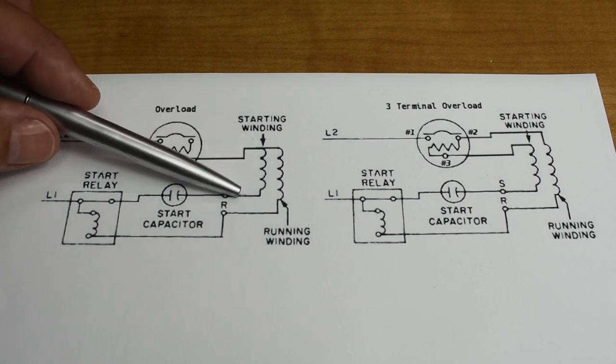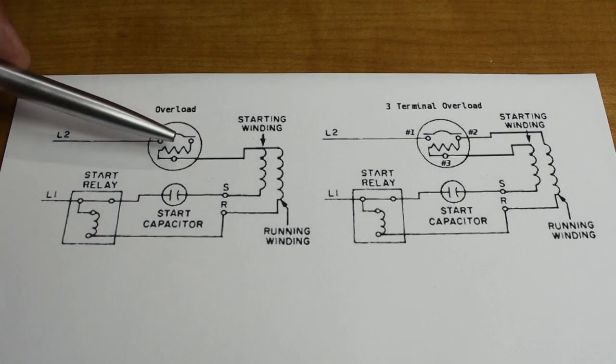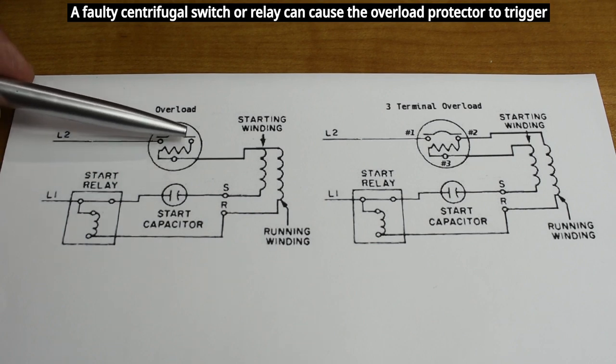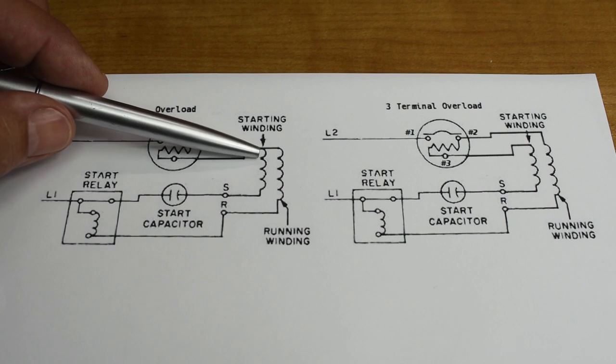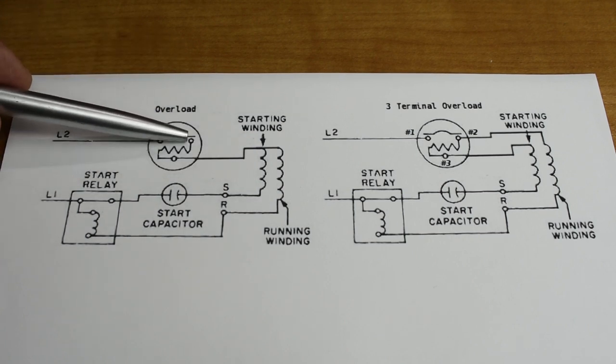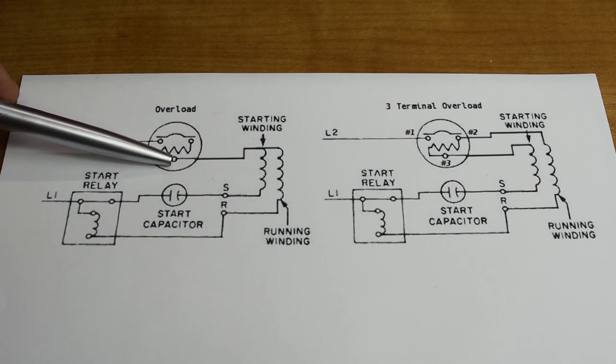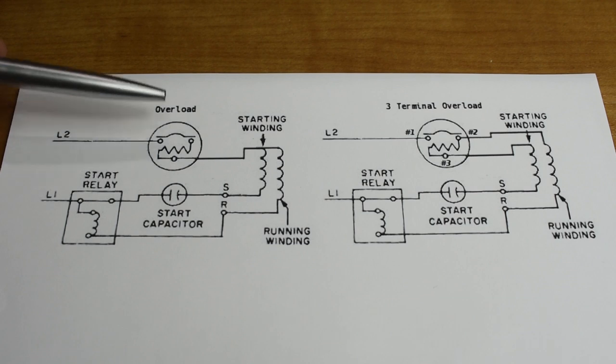Starting windings are only supposed to be connected up for a split second, just to get the motor to start, and then it's removed from the circuit. So if you have a problem with the start capacitor, if the value has become way too low or it became short-circuited, you're just going to hear the motor hum, it's not going to start up. This winding is going to become hot, and you're also going to have a lot of extra current flowing through the resistive element underneath that thermal disc, and it's going to cause the circuit to open up.